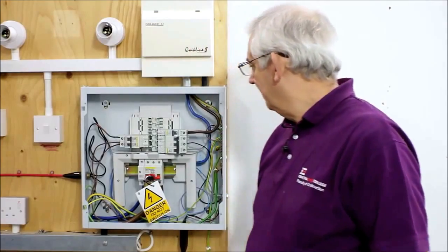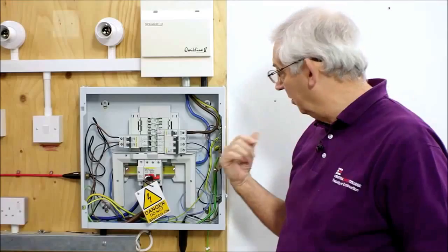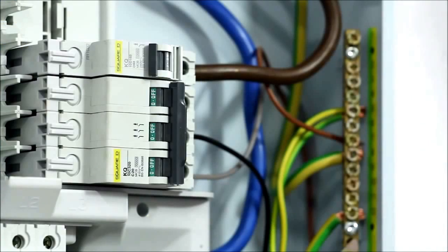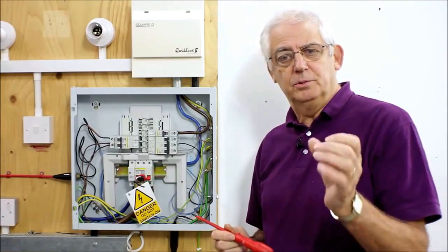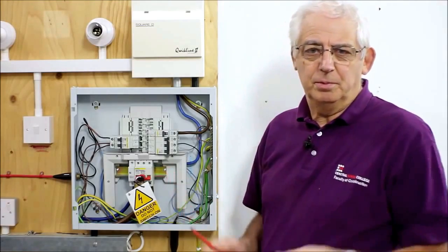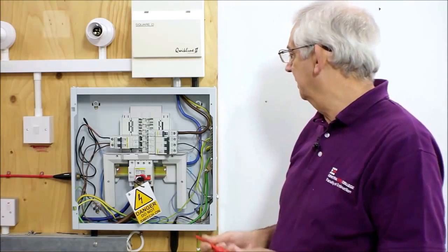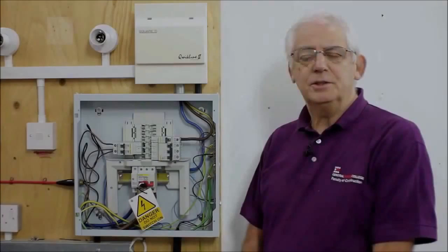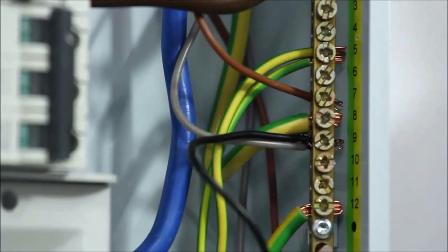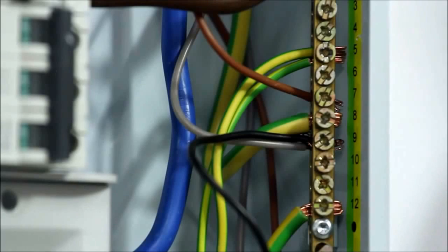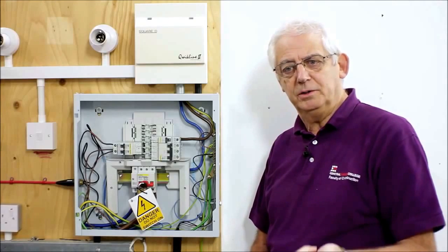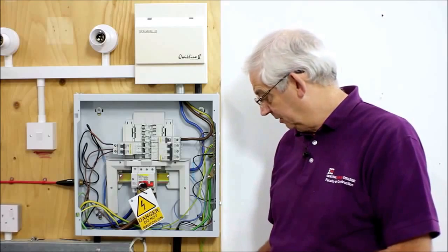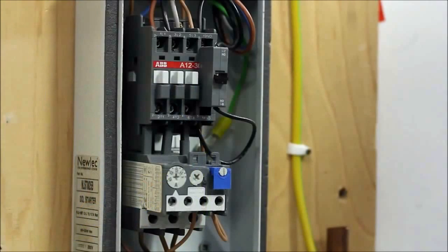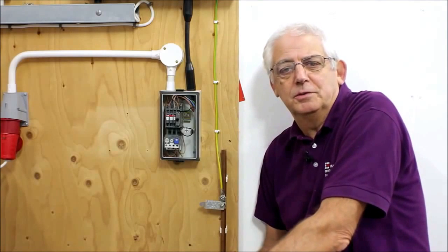Now I've done that, I need to connect each phase or each line into the earthing bar. The easiest way to do that is disconnect each one individually and connect it into the earth terminal. I could, if I want, do them all together, which is probably for the sake of this the easiest way to do it, so that's what I'll do now. As you can see, I've connected all three of them into the earth terminal. It may seem a bit strange, but actually I'm still only going to be measuring L1, L2 and L3 individually because I'm going to bypass the starter. As with all motor starters, we've got an overload device, which obviously prevents the motor from overloading.